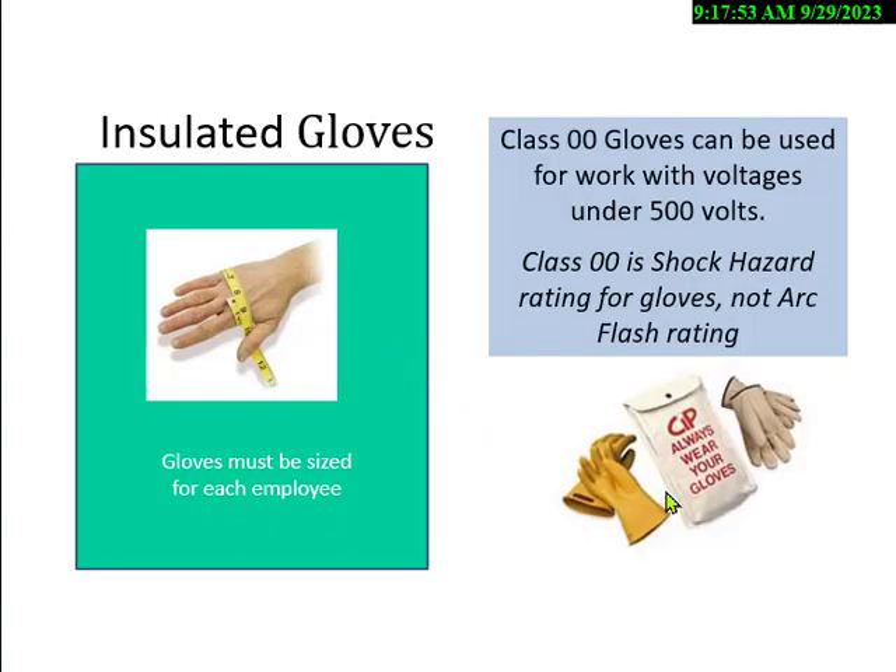Insulated gloves are made of rubberized material and are good for the voltage rating on the glove. Double zero is good for 500 volts. Class zero gloves are 1,000 volts. Class one is 7,500 volts. Class two is 17,000 volts and so on. You measure by hand size using a cloth tape — they come in half sizes, so I wear size 9. You also have to test these gloves on a periodic basis.